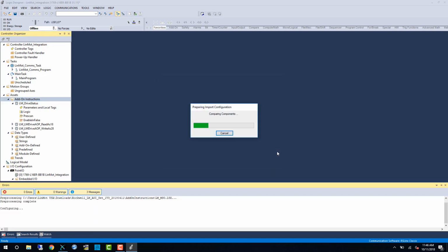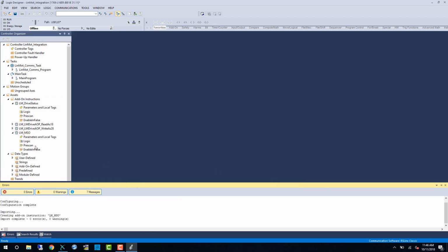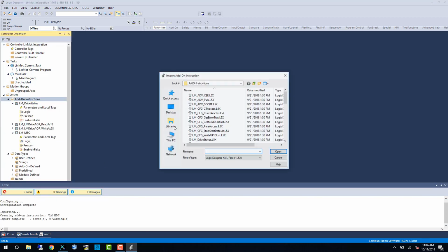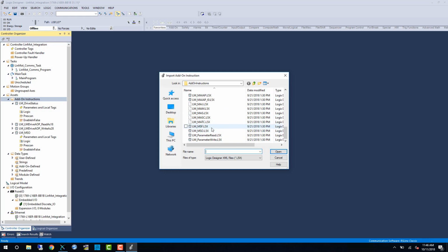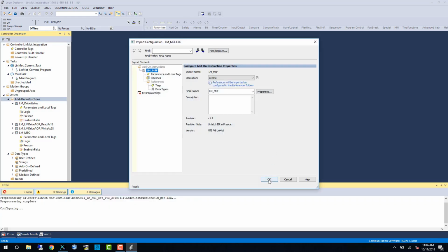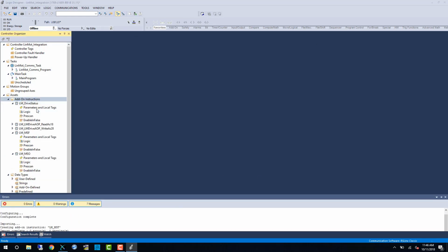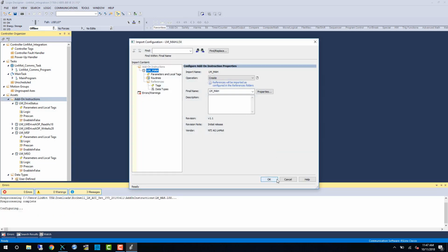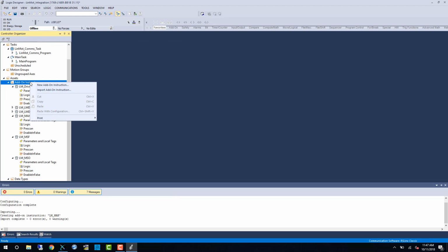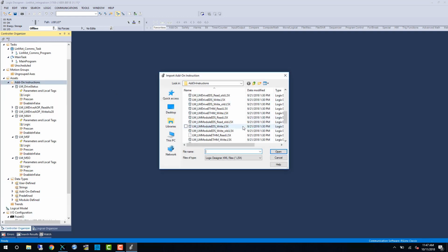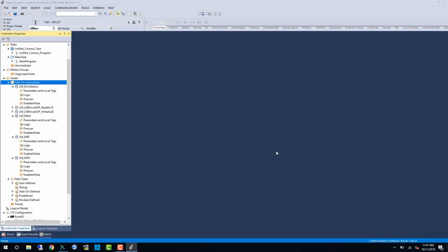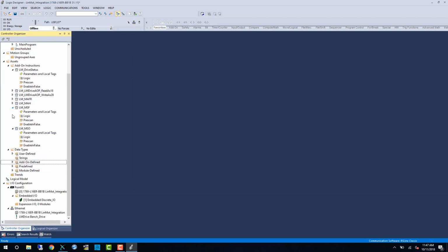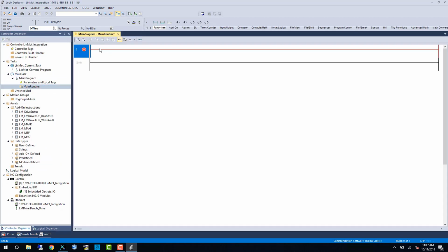The next AOI we're going to add is the MSO to switch on the drive. And here will come the MSF, the switch off command for the LinMot drive, the LMMAH to run our homing sequence as part of our initialization, and the LMMAFR to acknowledge any errors that might occur during operation.